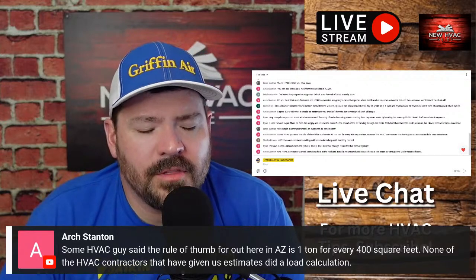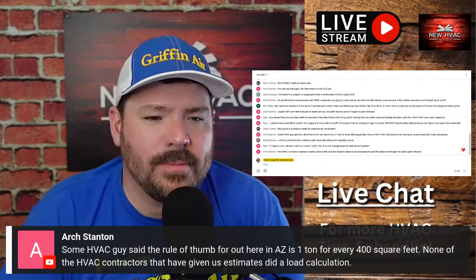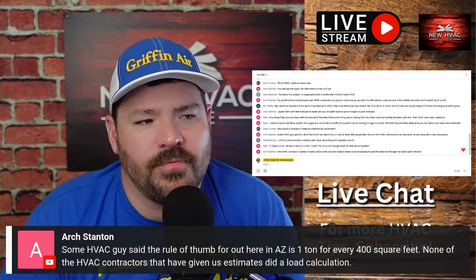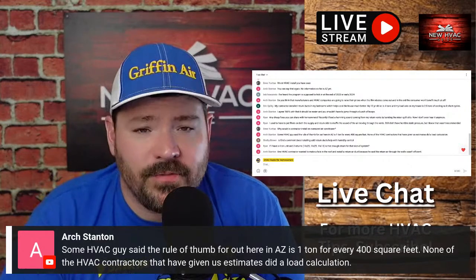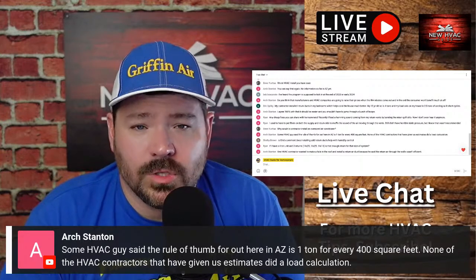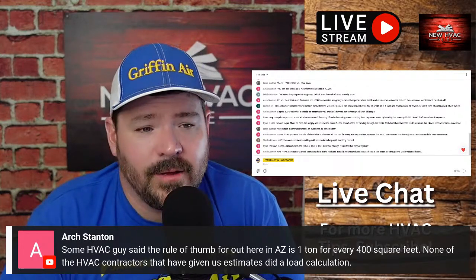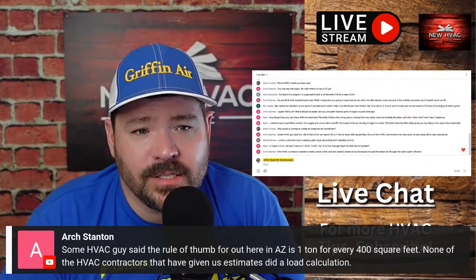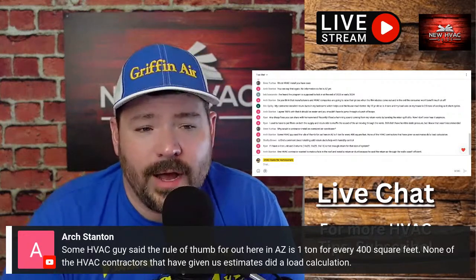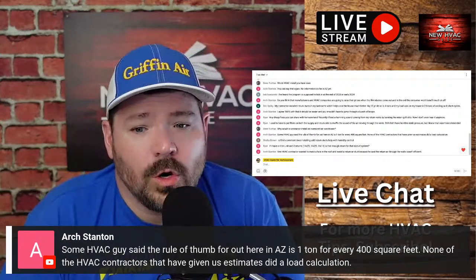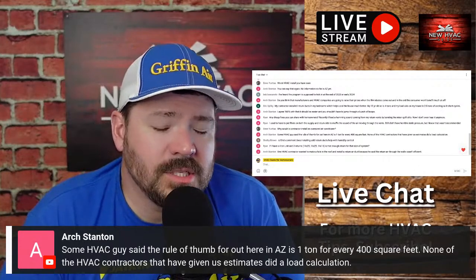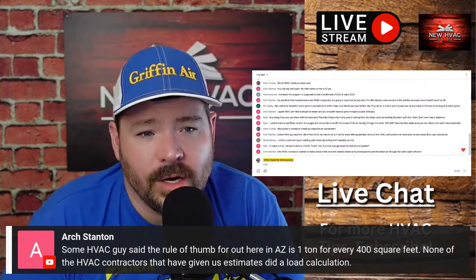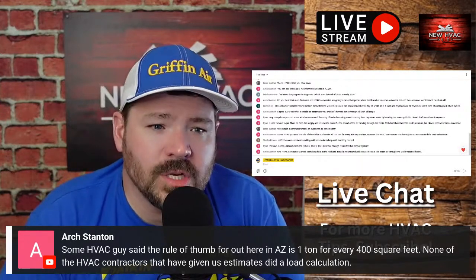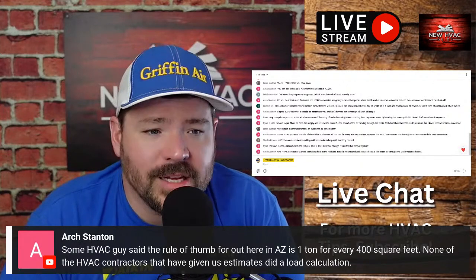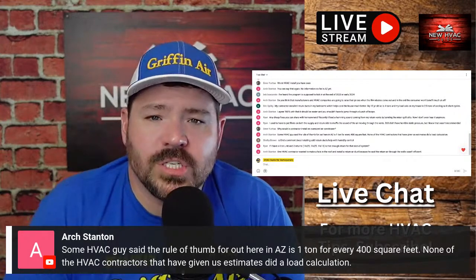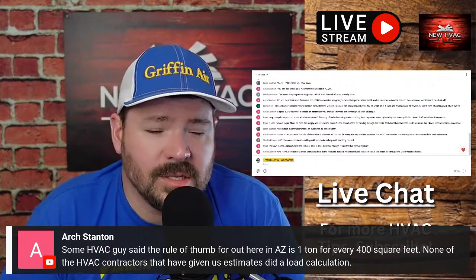I've seen stuff online where websites say if your house is this many square feet, you need this size unit. The problem is not all square-foot houses are created equal. You could have a 2,000 square foot house with 8-foot ceilings versus one with 20-foot vaulted ceilings, one in full sun versus one shaded, one in a humid environment versus another. There are so many variables—number of windows, the R-value of insulation. Going by square footage alone is simply not the best way to do it. It's not even a good way to do it.